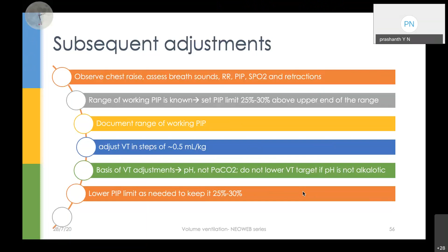And based on the clinical response, we can adjust VT in steps of 0.5 ml per kg, because the range we said is between 4 and 6.5. So you can go up or come down, but definitely not less than 4. When we adjust VT, the tidal volume should be adjusted primarily with the pH, not with PCO2, because we know the tidal volumes are set. It cannot increase beyond 6.5 to 7, and it cannot decrease to less than, say, 3.5 or so. So we need to see the pH. A lower PIP limit can also be set in some ventilators, and it should be kept at around 25 to 30%, and it could also serve as the alarm limit for you.